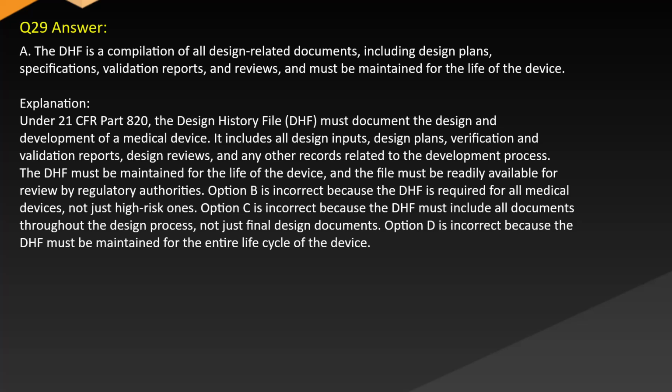Option B is incorrect because the DHF is required for all medical devices, not just high-risk ones. Option C is incorrect because the DHF must include all documents throughout the design process, not just final design documents. Option D is incorrect because the DHF must be maintained for the entire life cycle of the device.